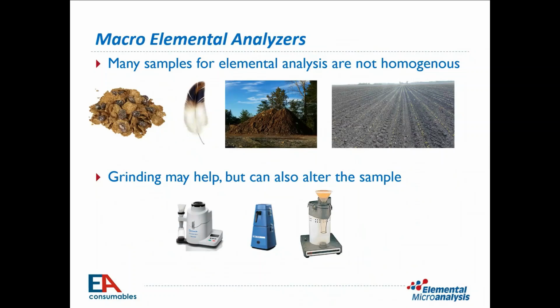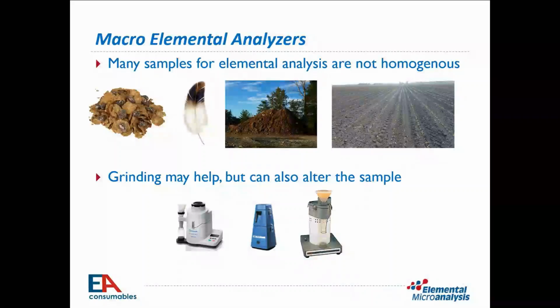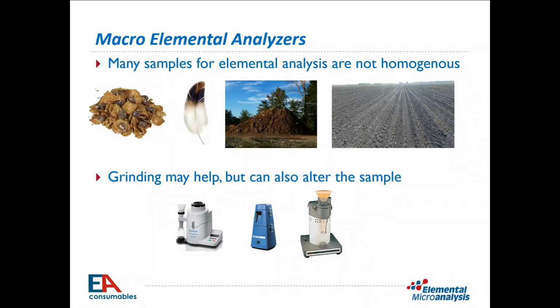There is also another class of analyzers in elemental analysis, which are called macro-elemental analyzers. Mainly, we want to analyze a larger sample to overcome inhomogeneity issues. How much sample should you use? The old adage is as small as possible, but as large as required, which is kind of confusing. Less sample means less time of analysis and fewer reagents used in the analyzer, but for some samples, too small a sample size can lead to very non-representative results.